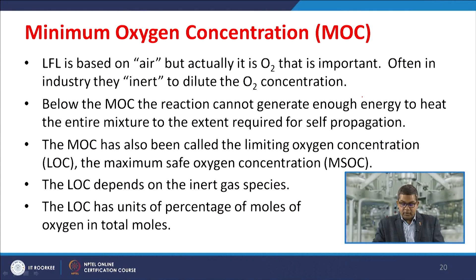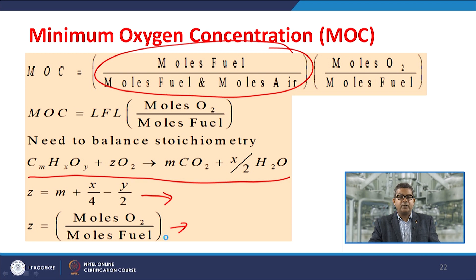Now this is the mathematical relationship, or a derivation, through which you can theoretically calculate the minimum oxygen concentration. The minimum oxygen concentration is equal to moles of fuel divided by moles of fuel plus moles of air, multiplied by moles of oxygen divided by moles of fuel, and this first term is the LFL. So MOC is equal to LFL times moles of oxygen divided by moles of fuel. So you need to balance the stoichiometric relationship. This is the generalized hydrocarbon combustion relation: CmHxOy plus Z O2 gives m CO2 plus x/2 H2O. Through this you can calculate Z, which is equal to m plus x/4 minus y/2, where Z is moles of oxygen divided by moles of fuel. So you can easily calculate the minimum oxygen concentration.